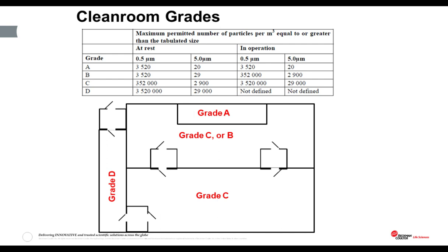People are the biggest source of contamination in the clean room environment. Workers in clean rooms have to pass through several different classes of clean room to enter the production suite. Each area is separated by an airlock, which minimizes the flow of air from dirtier outer rooms into the clean production areas. Particle counters also have to be sanitized as they move through each grade of clean room, typically by spraying them with an industrial alcohol called IPA.